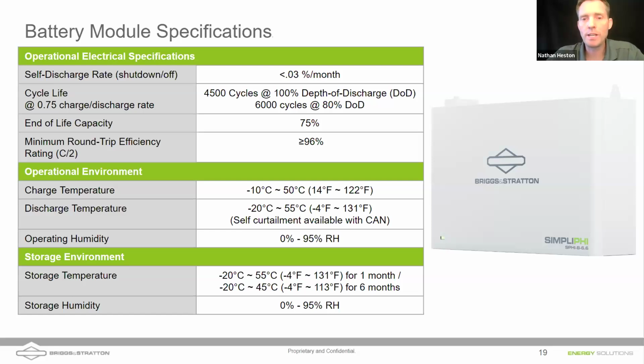We can charge this battery below 32 degrees Fahrenheit, and that's not typical. Most companies have a lower range of 32 Fahrenheit, but we can charge this battery all the way down to 14 degrees Fahrenheit, because of an advancement we've made with the electrolyte inside these cells. Discharge temperature goes all the way down to -4 Fahrenheit. The charging window is a little more restrictive, but still, having that range down to 14 Fahrenheit opens up a lot more markets.